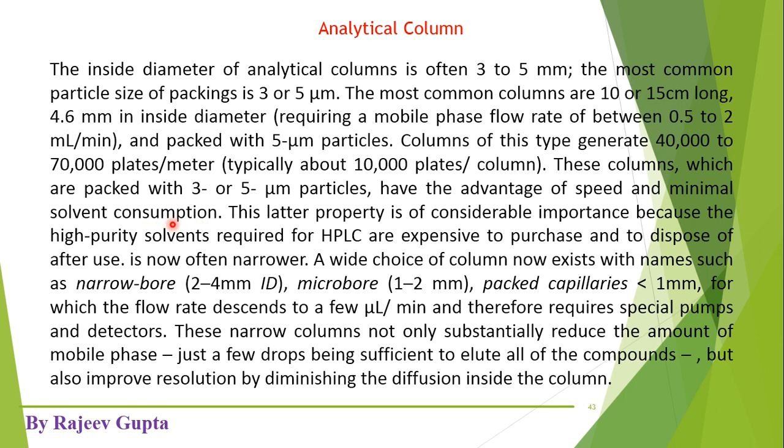Also, the solvent consumption is very low, because the maximum flow rate is 2 ml per minute, meaning only 2 ml of solvent is consumed per minute. So if our experiment runs for 5 minutes, only 10 ml of solvent is consumed for one sample. It is a very low amount of solvent used for the analysis of our sample in HPLC.